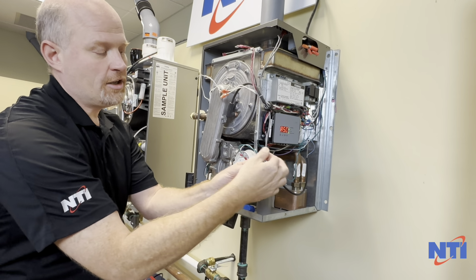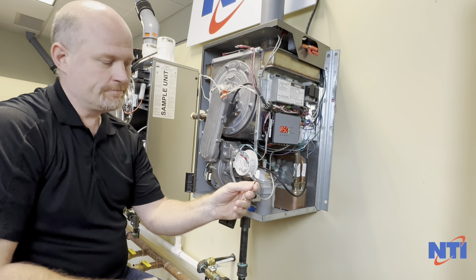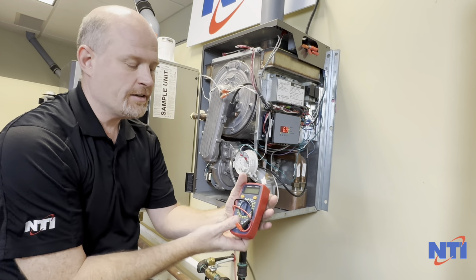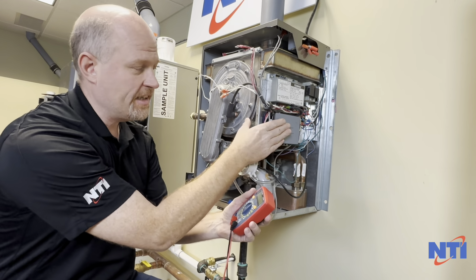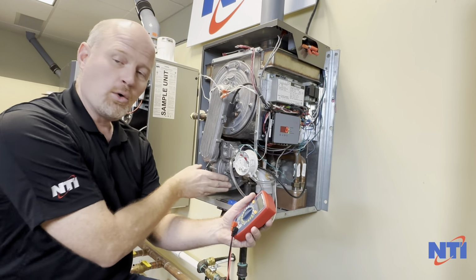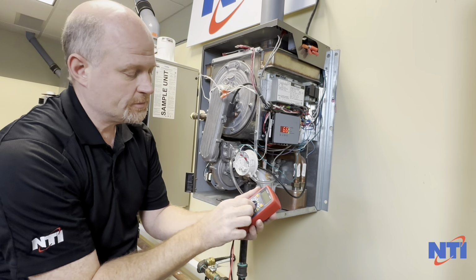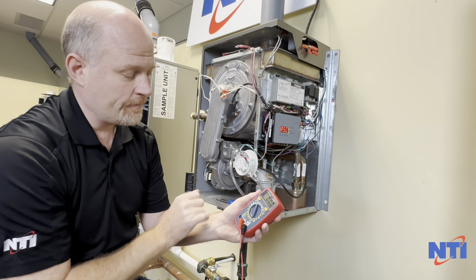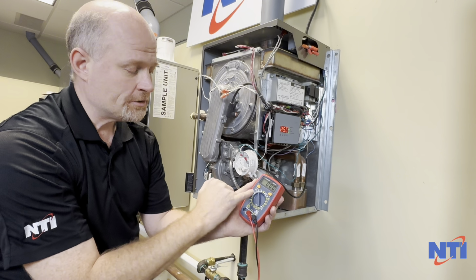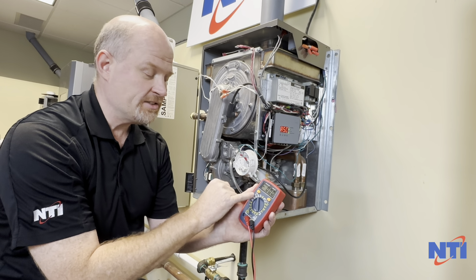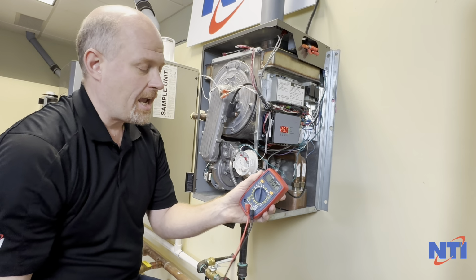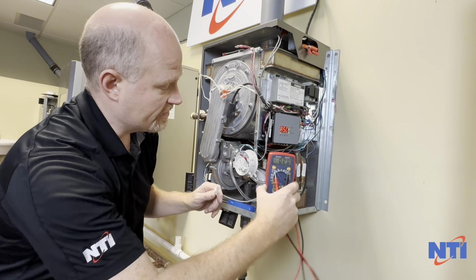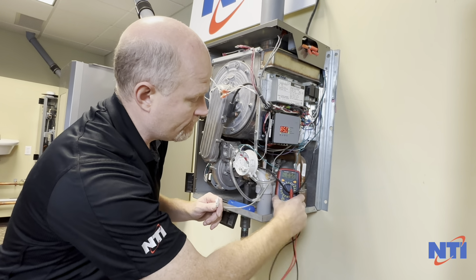And you're going to look at the black and the red. And what we want to do here is when you have the fan running and it's not supposed to be, possibly this is sending the wrong signal or the blower's receiving the wrong signal. So we're going to go to volts DC. I'm going to set it on my meter to the range of 200, and that's because the signal we're looking for is about 35 to 38 volts.